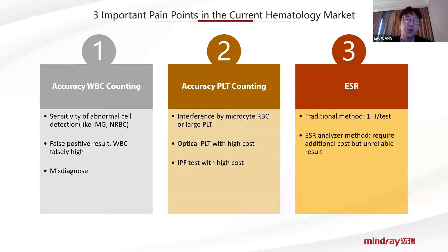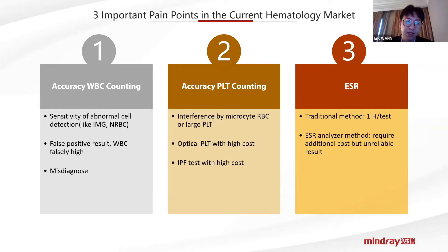We realized that there were three main concerns in the current hematology market. People need accurate white blood cell counting, especially for reliable abnormal cell detections, like immature granulocytes and nucleated red blood cells. People want to remove interference — like micro-sized red blood cells, fragmented red blood cells, and large platelets — when counting platelets. People also have requests for IPF parameters, and what more can we do for the ESR test. Based on these concerns, we developed this new generation.